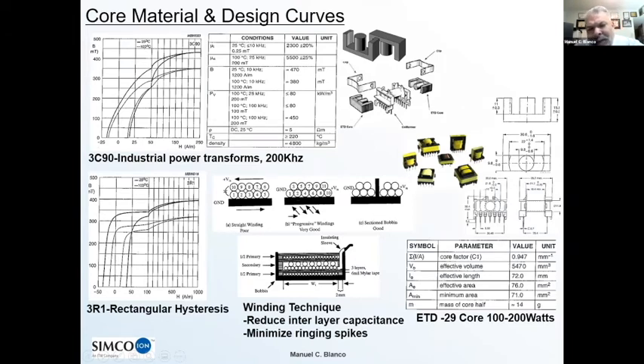A lot of the intricacies in winding have to do with leakage inductances, because you don't want a lot of leakage in your transformer, since it'll build up as heat. And as I said before, the heat has got to go somewhere. So if it's not being efficiently transformed into your load, that's something you'll have to deal with in your design.